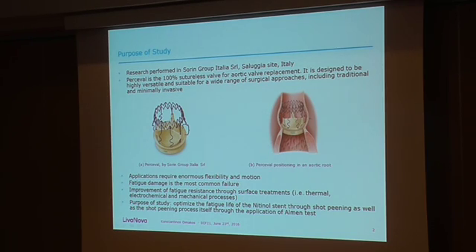My project is mainly based on Perceval. Perceval is a 100% sutureless valve for aortic valve replacement. And it's mainly used for surgical approaches, including traditional and minimally invasive. So what happens is that this material, the nitinol stent, as you can see here, this is the way it's implanted inside the aortic root. So the way it's implanted in there, it's collapsed through a particular accessory that we have that our company produces, and then it's expanded.